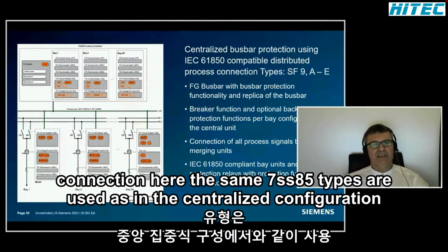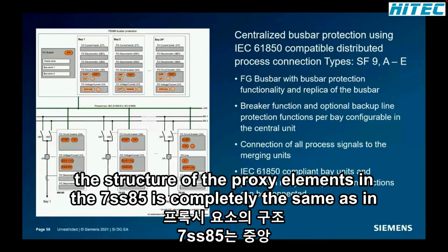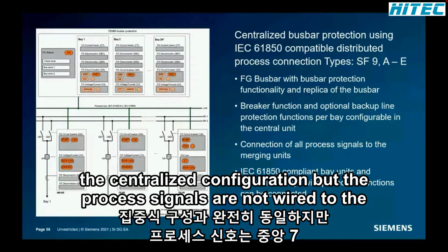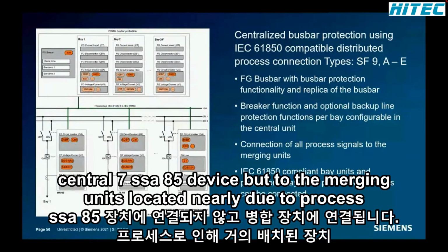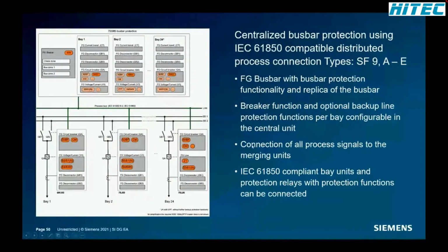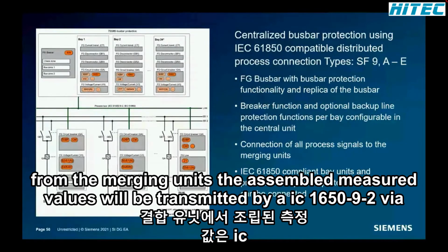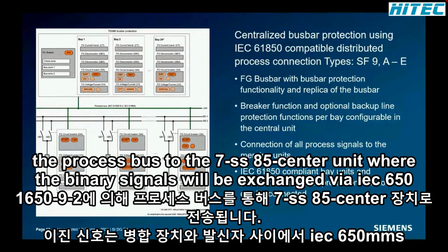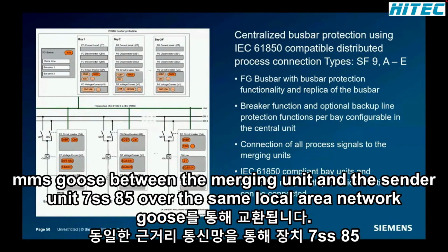Here the same 7SS85 types are used as in the centralized configuration. The structure of the proxy elements in the 7SS85 is completely the same as in the centralized configuration. But the process signals are not wired to the central 7SS85 device, but to the merging units located nearly to the process. From the merging units, the sampled measured values will be transmitted by IEC 61850-9-2 via the process bus to the 7SS85 center unit, where the binary signals will be exchanged via IEC 61850 MMS GOOSE between the merging unit and the center unit 7SS85 over the same local area network.